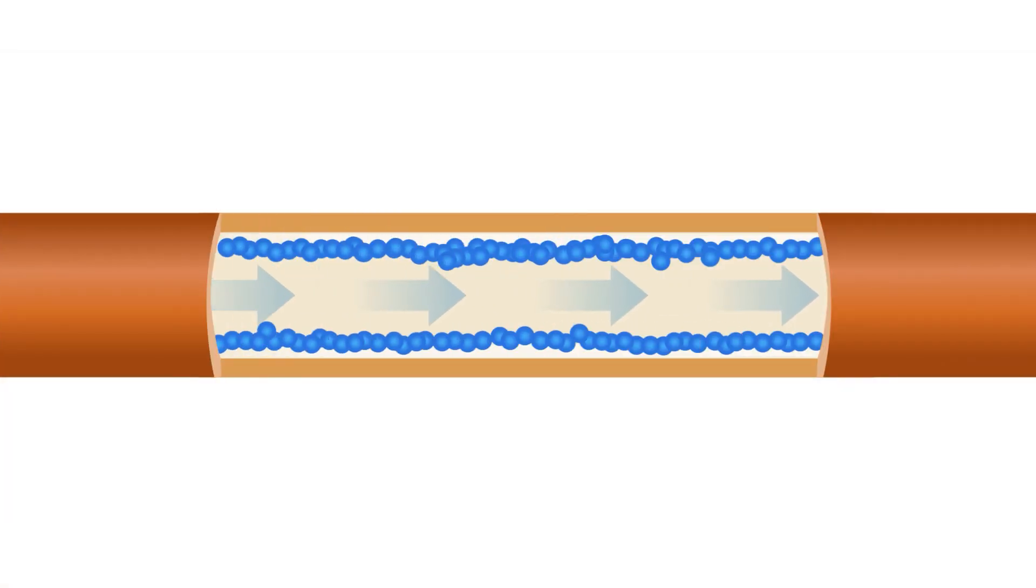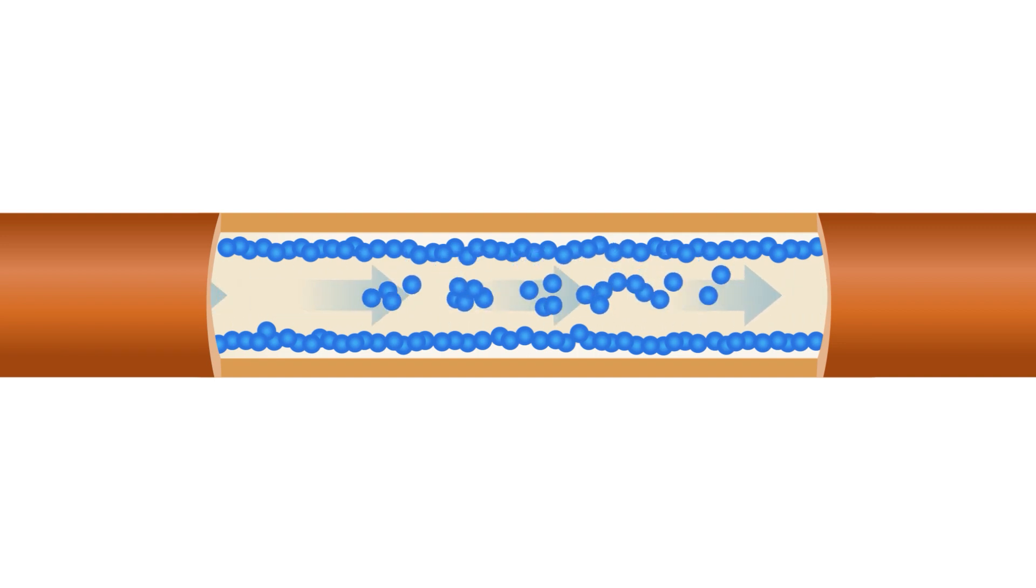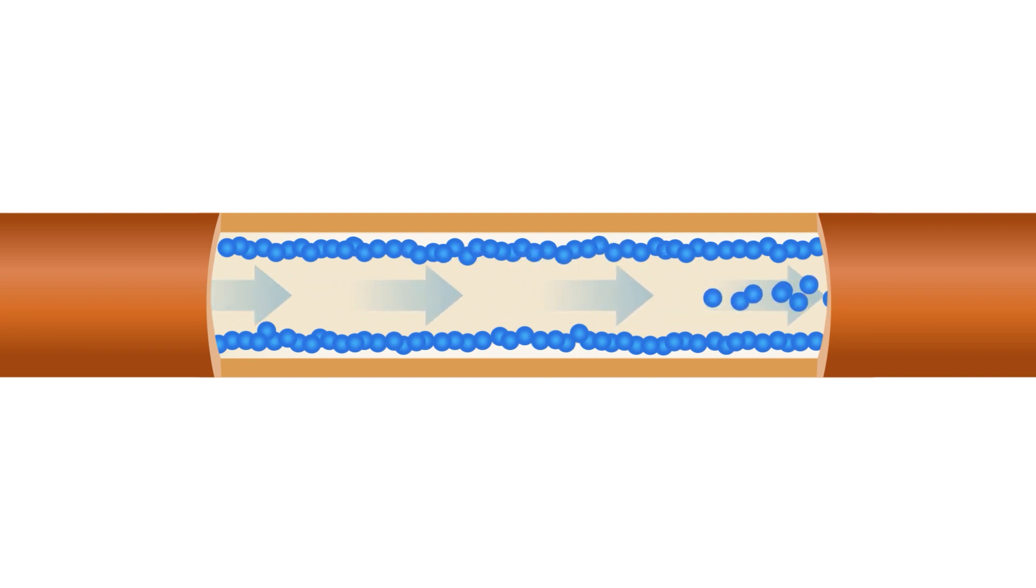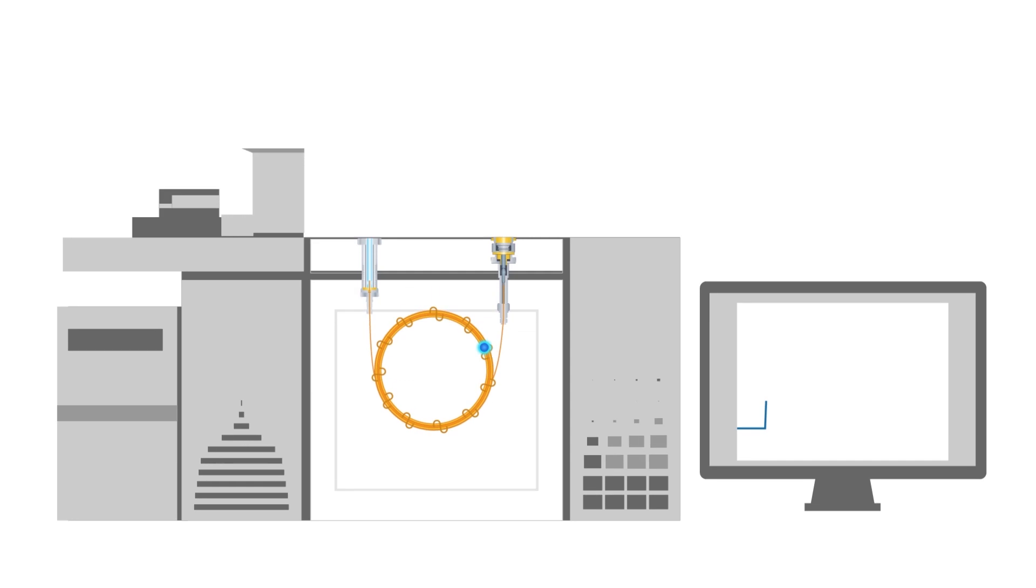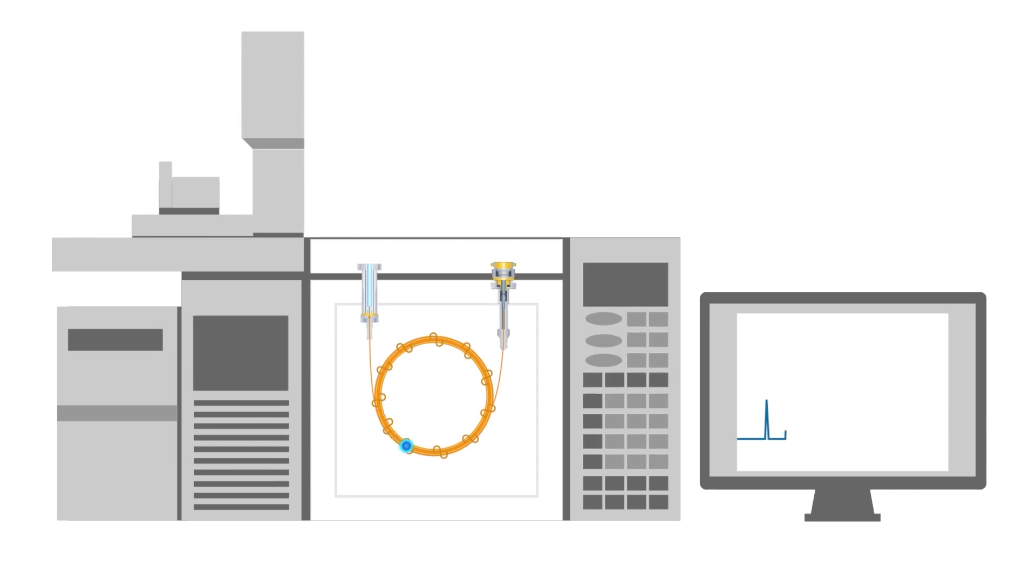Nevertheless, during transportation, gas flow changes, or valve switching, some particles may dislodge and release from the column. These particles can then cause spikes in the chromatogram or damage switching valves, leading to time-consuming and costly side effects.